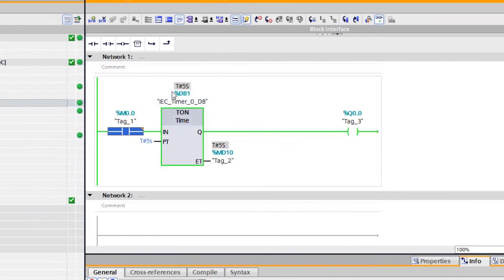Right-click, Modify, set to 0. Now you can see the output goes OFF the moment I close the input. I will start the input again — Modify to 1. The timer starts but there is no output yet. Once the timing is done, you can see the output goes high. This is an on-delay timer — it takes some delay to switch ON, that is the on-delay.